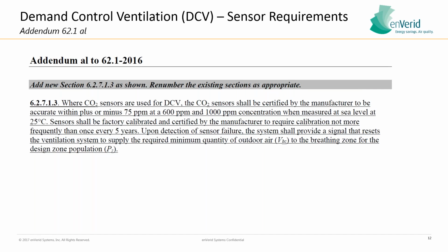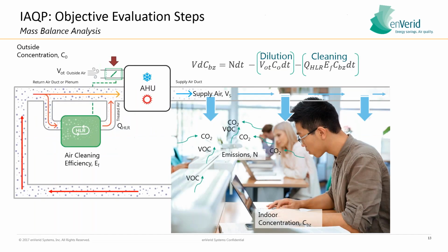Additionally, for demand control ventilation, there was an addendum to 62.1-2016 that says that sensors shall be factory calibrated and certified by the manufacturer not more frequently than once every 5 years. So it's getting a little bit more specific on the frequency of calibration for sensors and the requirements surrounding demand control ventilation. The indoor air quality procedure is actually a fairly straightforward procedure. Don't be scared of that calculation up there at the top. We'll walk through it very quickly here.